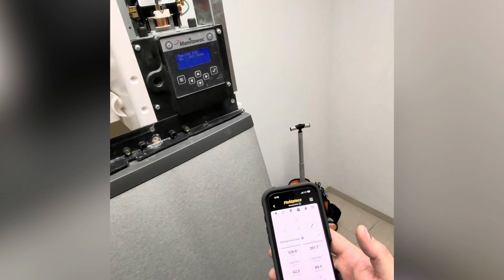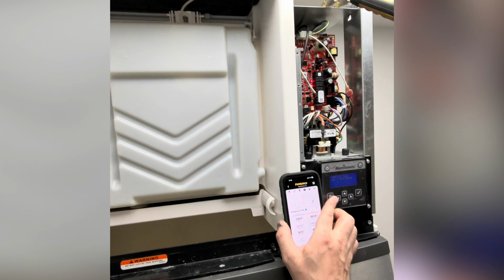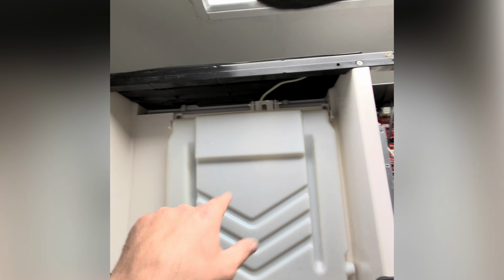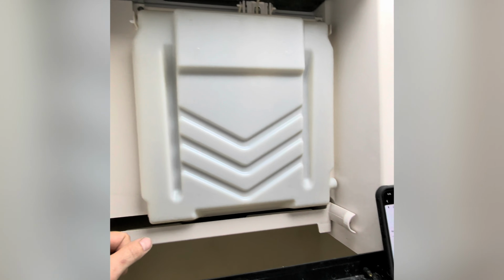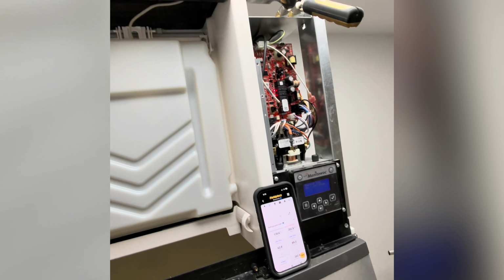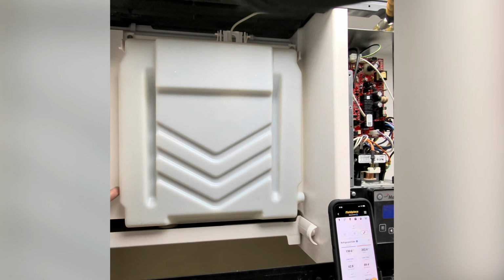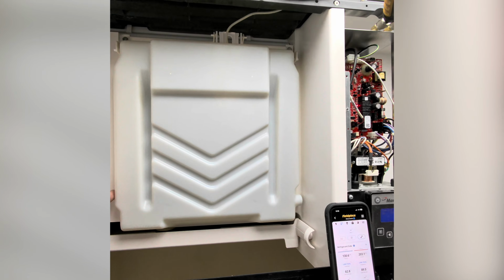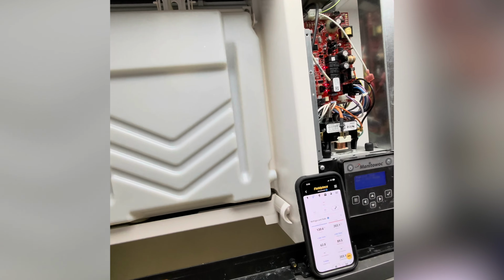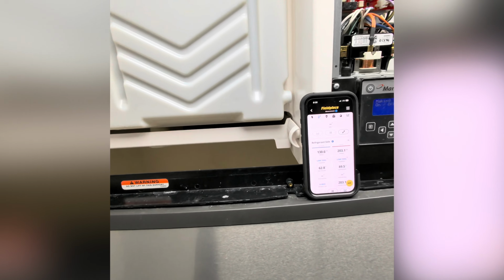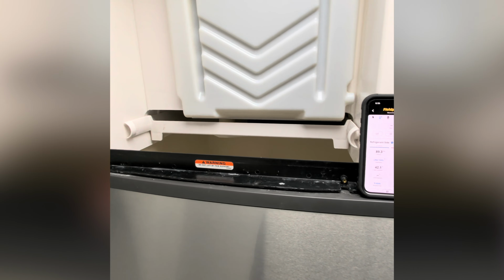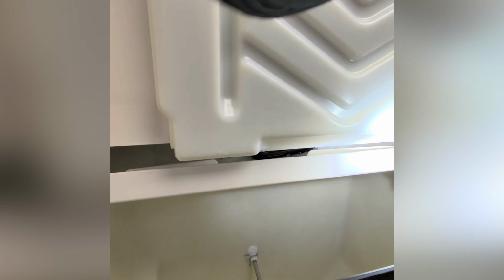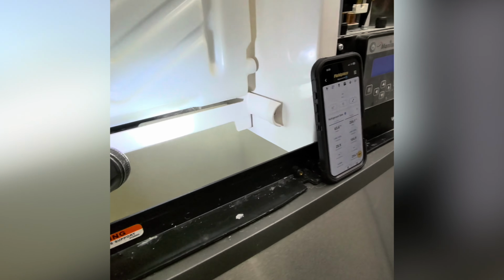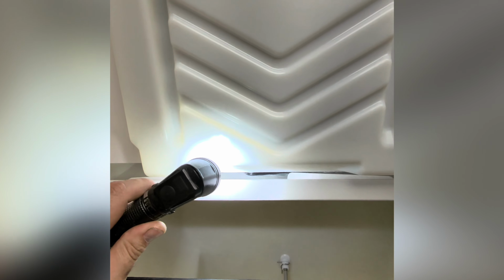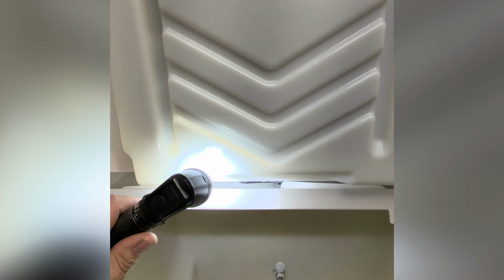Reset the unit and now it's working, so we're going to watch it go through a cycle, possibly adjust the ice thickness as we need to. Let's go into ice mode by just cycling this curtain. Pressures should start coming down. Yeah, water's filling very great, pretty quick. Much better than before. Let's see where the water cycles off.